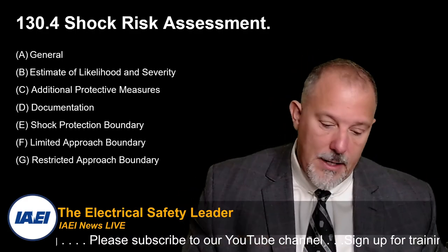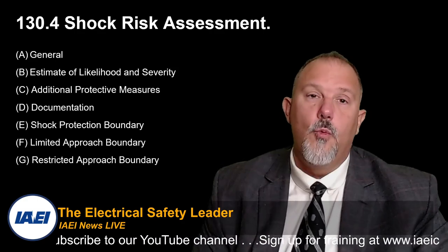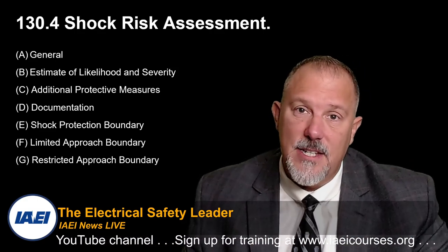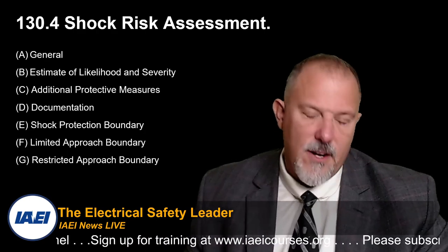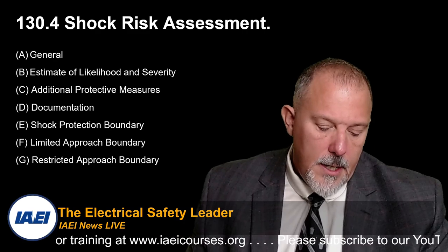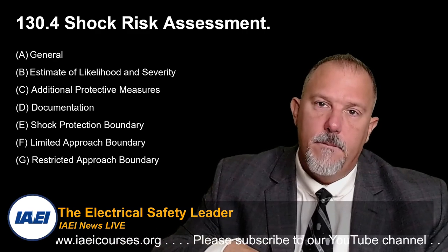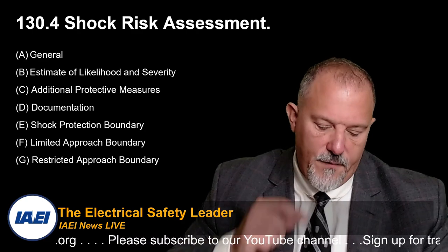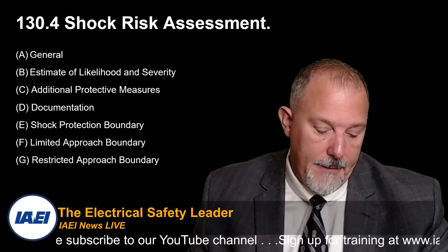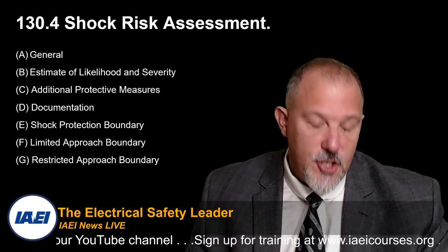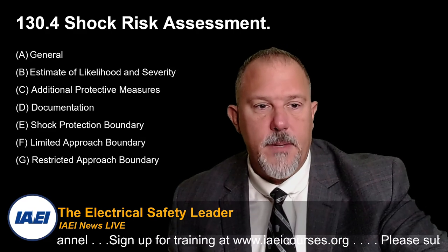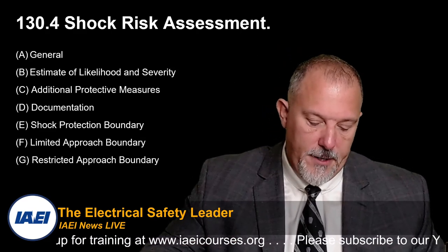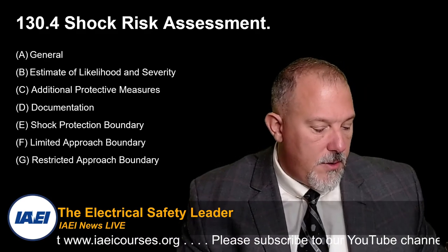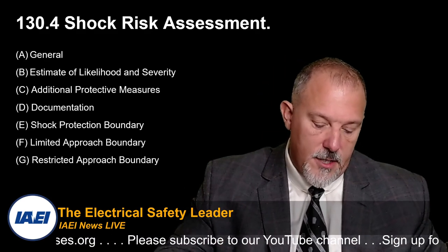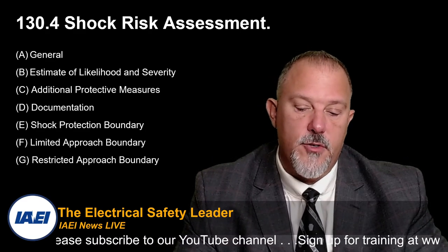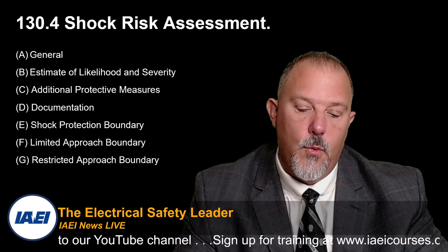You document this. Then you get into your shock protection boundaries, understanding what your distances are. Remember that 3.5 foot, 3 foot 6 inches, up to 700 and some volts, right? 750 volts, I think it is. And this is where you'll find your boundary distances, your table 130.4 E A, and that's your shock protection boundary. F is your limited approach boundary. Now, you have a shock protection boundary, you have your limited approach boundary. Now, for your limited approach boundary, there's a different table. That would be found under limited approach boundary is permitted by 130.4F3.